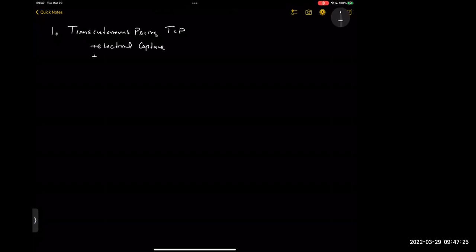So you put the pacer slash defibrillator slash cardioversion pads on the patient, and then you initiate pacing, setting the rate that you want, and starting at your low output, moving up to high output, and you look for two things. The first thing you look for is what we call electrical capture. And then you verify the presence of mechanical capture. You ensure that the rate you set on the pacemaker matches the rate that you can palpate. And so that's fairly straightforward.